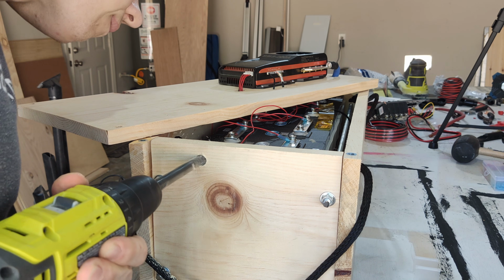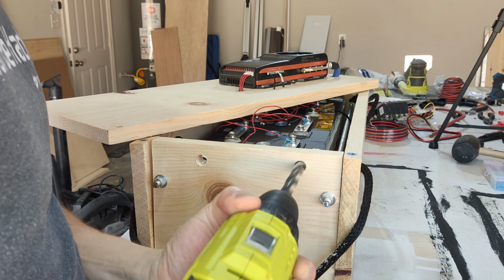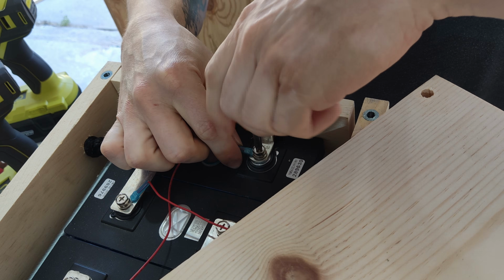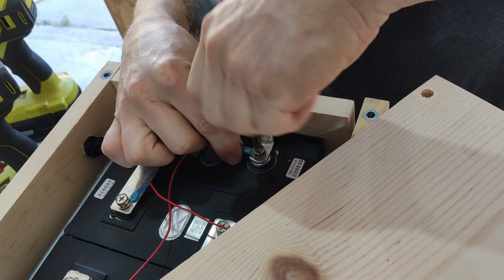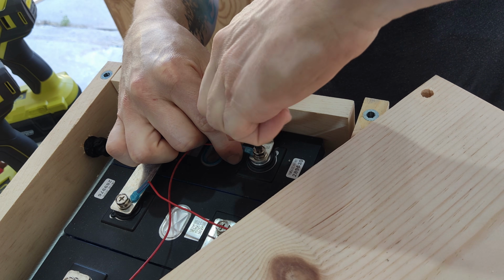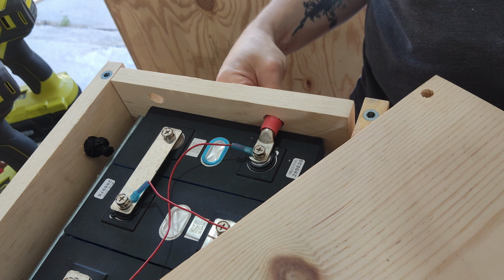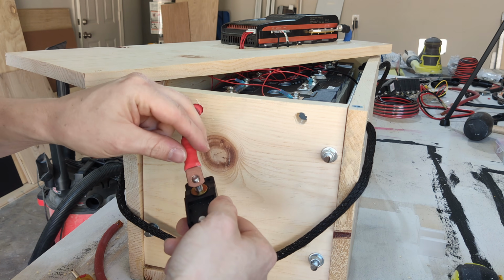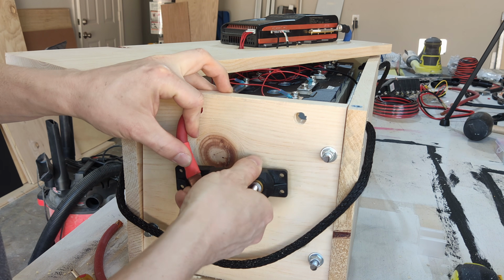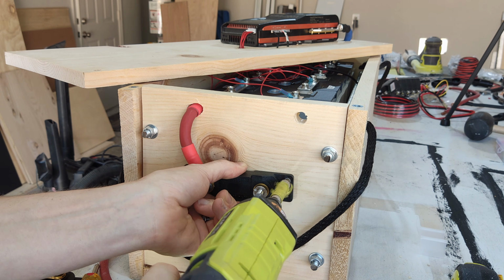It's also very important when you have batteries in parallel that the run of cable from the bus bar to the battery cells themselves is the same exact distance. If there are different distances, you're going to have different loads and discharge rates on the batteries, and over time that will lead to an imbalance of your cells.